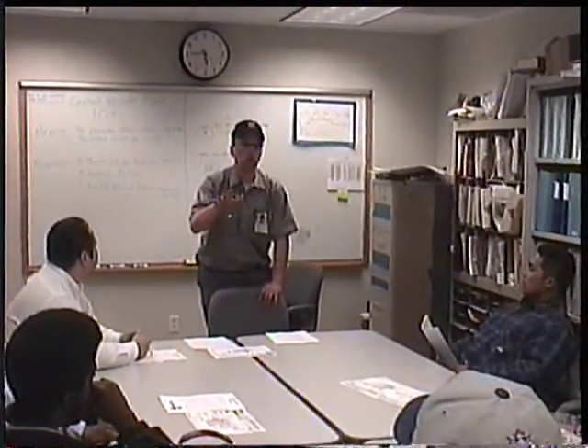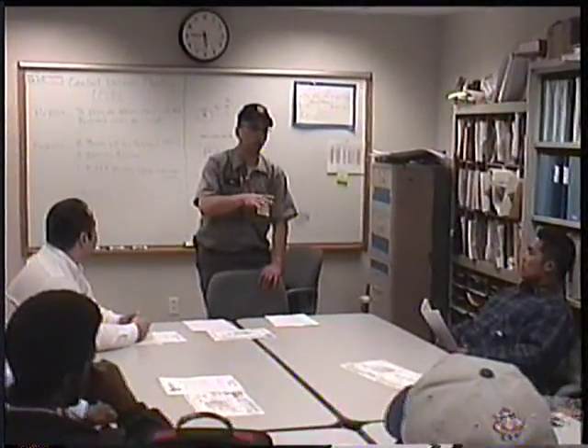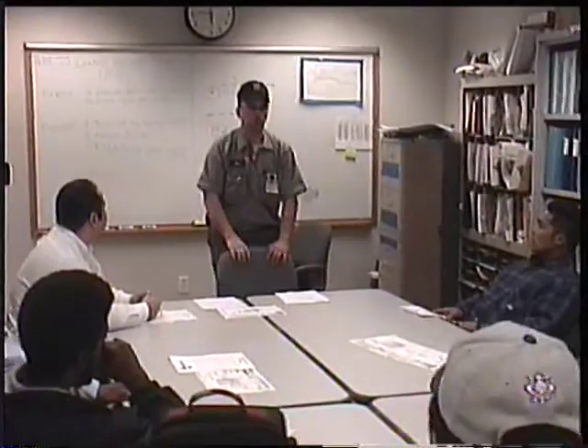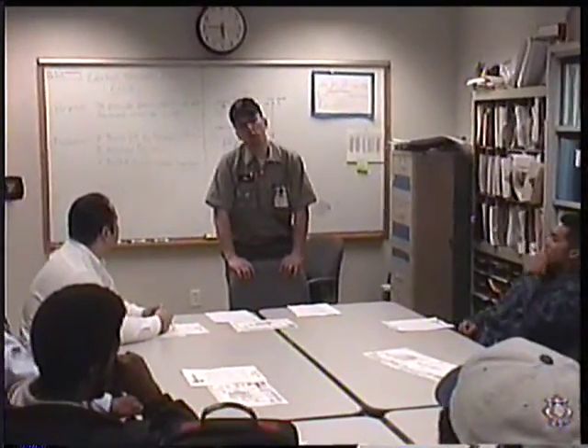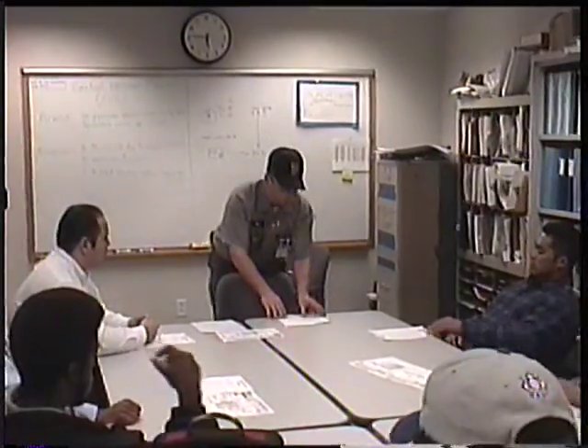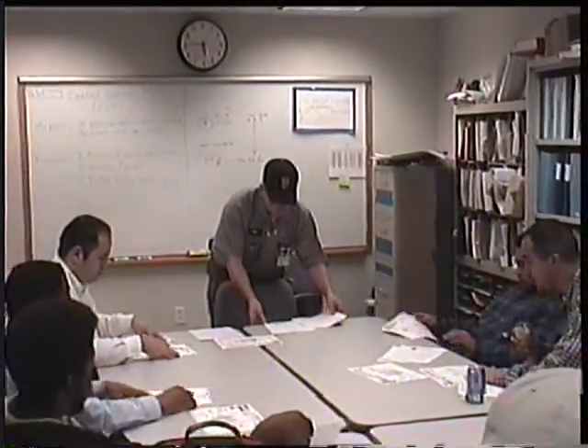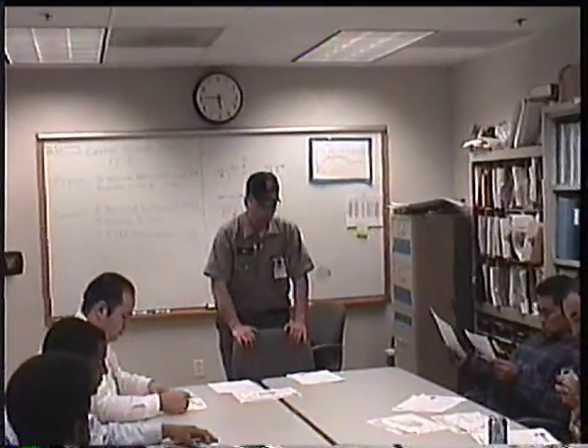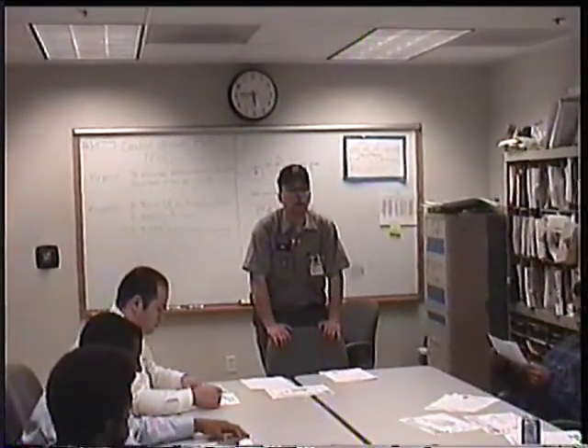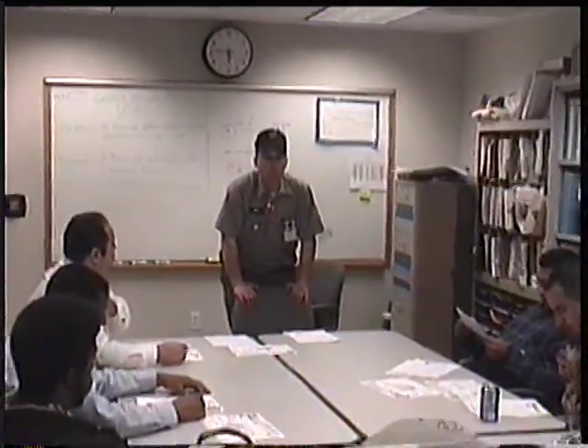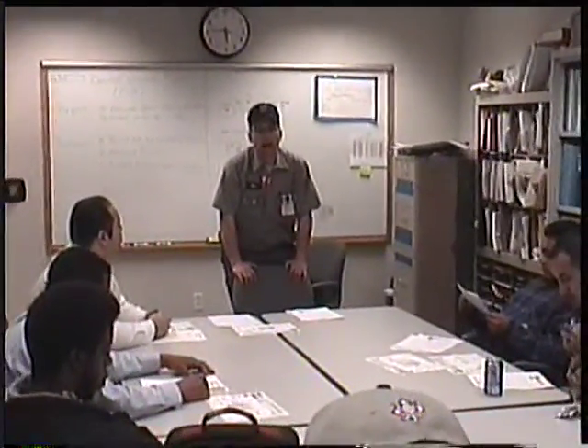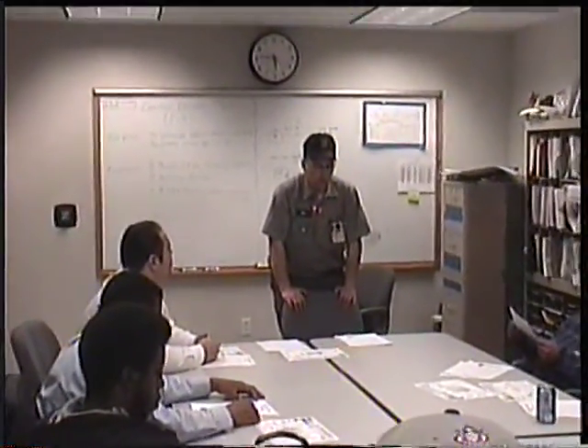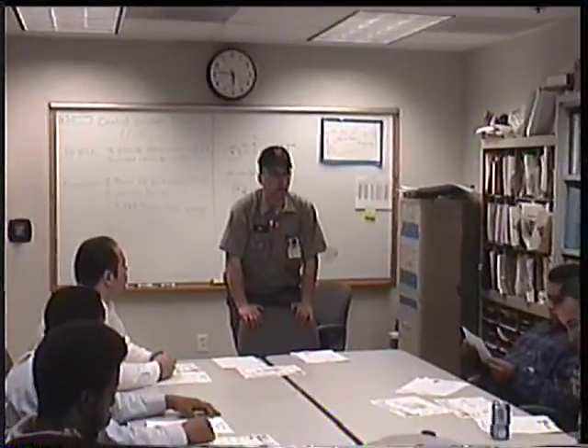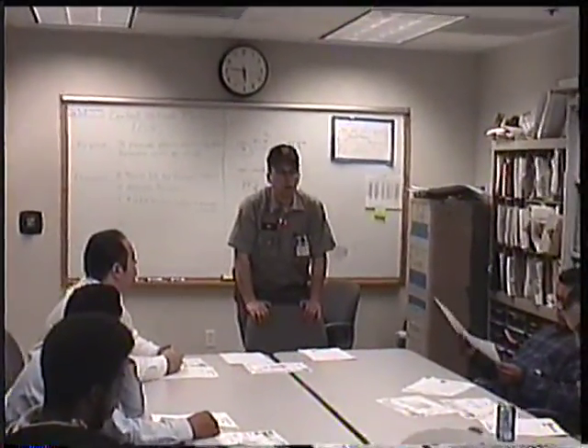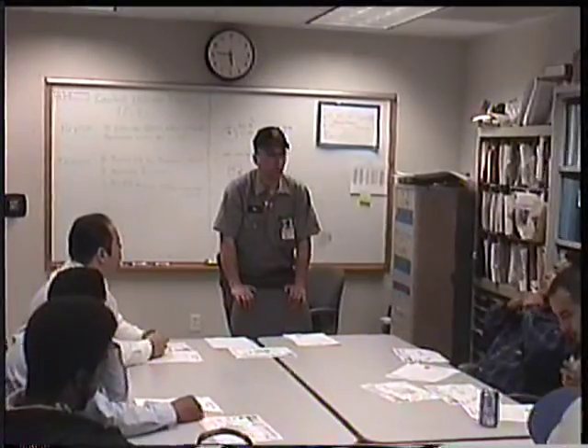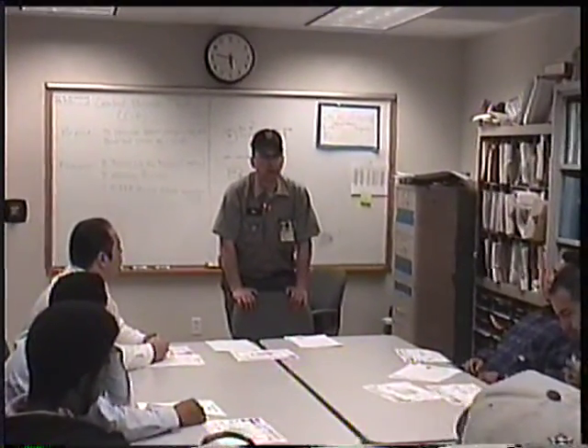I'm just going to go briefly over the HRSGs because we're more into boilers. Even though the HRSG is a boiler, it's a totally different setup than anything we've been studying. We also have 2 Nebraska boilers, which you have a spreadsheet on, a contract data boiler. Nebraska boilers are capable of producing about 90,000 pounds of steam per hour each, although we usually don't call for anywhere near that. The reason we call them aux boilers is simply that that's what they are. They're auxiliary boilers, not primary boilers at all. They're only used, for the most part, when there's a heavy steam demand on campus and the HRSGs can't keep up.